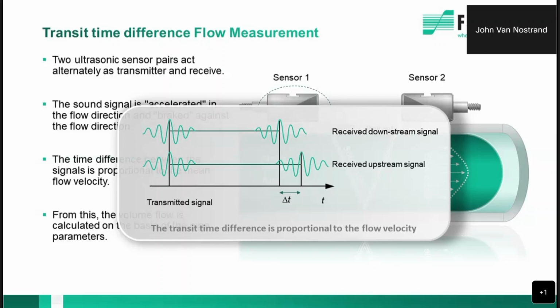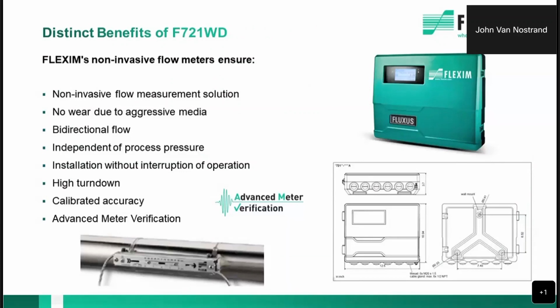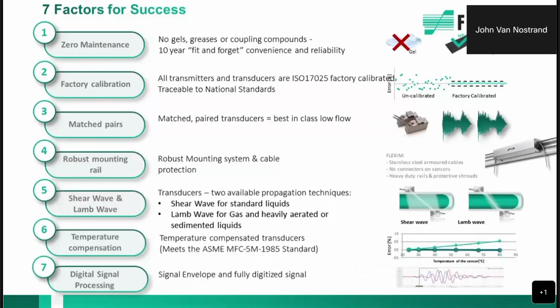So as far as flow measurement goes, we're measuring velocity just like any other type of flow meter and calculating volumetric flow based on the area of the pipe. We're just doing it with a transit time signal. The 721 is the meter of choice for water applications and wastewater applications. It's sold as a package, meaning that there's one part number that includes the meter, the transducers, and the tracks, the mounting hardware. Everything that you need for the meter is included in that part number.